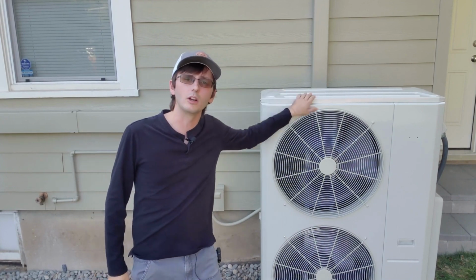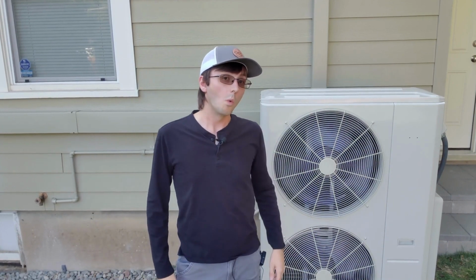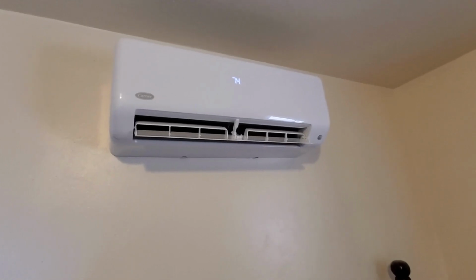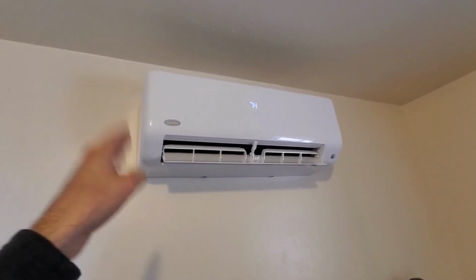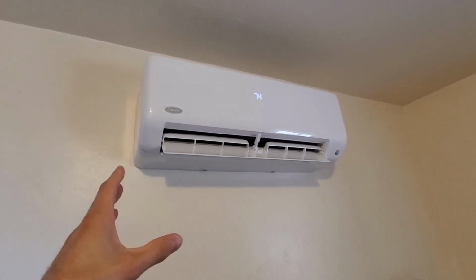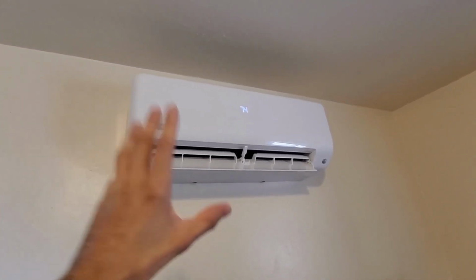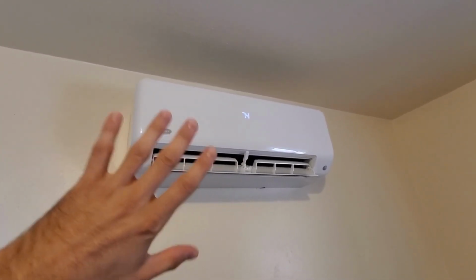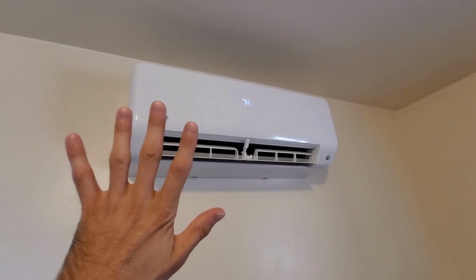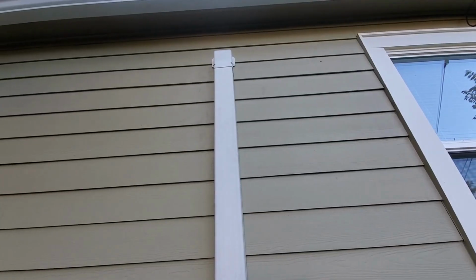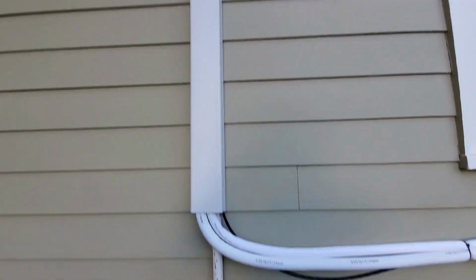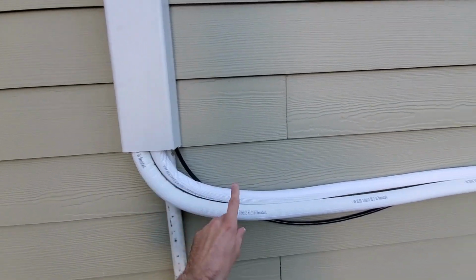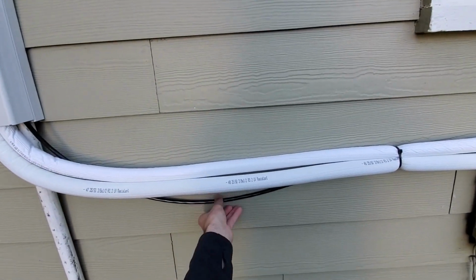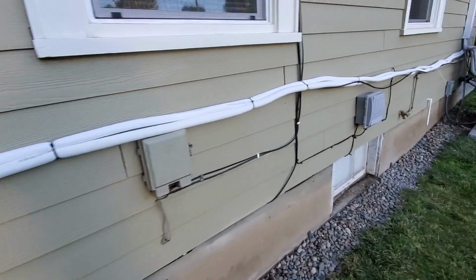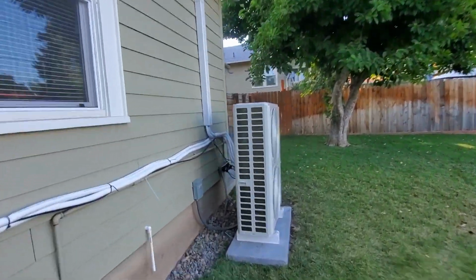This is the condenser unit right here. So first off, let's ask the question: what is a mini split? A mini split is simply a system where you have wall units, ceiling cassettes, or baseboard units that have temperature control per unit, with up to 1 to 5 zones typically. Instead of using ductwork to move air around, you just move refrigerant lines around. They consist of 2 refrigerant lines per unit and a communications cable, and they go up to multiple zones, up to 5.